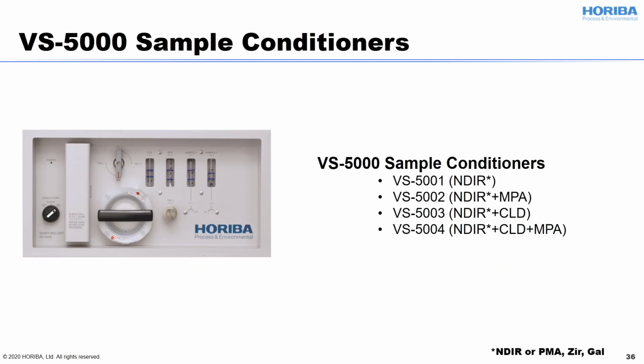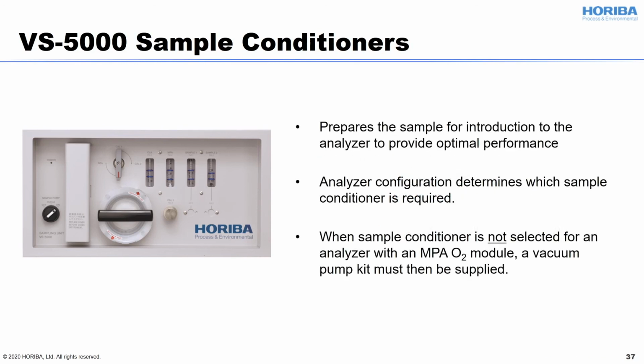Here's another option for the sample system, the VS5000. There are 4 types of sampling system according to the analyzer modules. Sampling system is used to treat sample gas for the optimal measurement performance. Basically, knock off the moisture and filter the dust, and proper pressure and flow is provided by using the sampling system. Especially MPA O2 is very sensitive to the pressure, so proper design of the sample system is required.